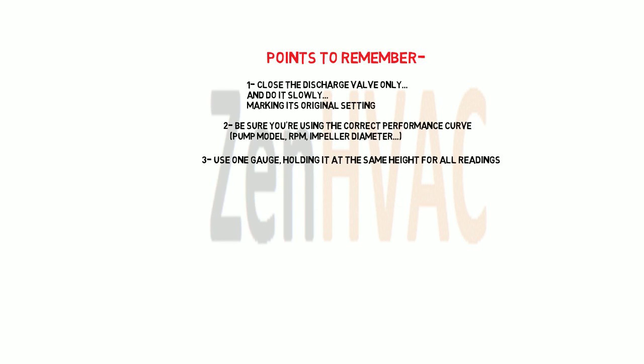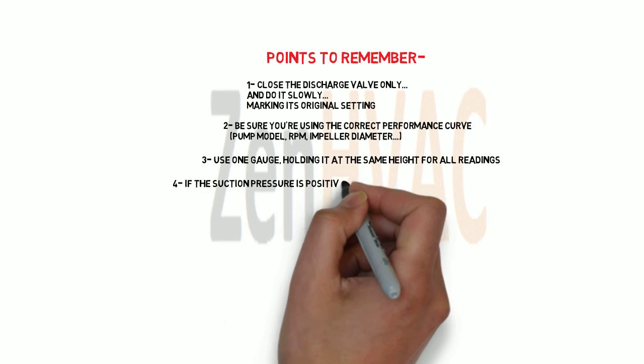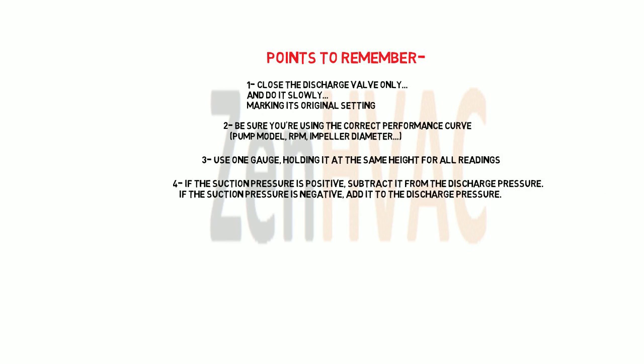Three, use one gauge, holding it at the same height for all readings. It makes a difference. Four, if the suction pressure is positive, subtract it from the head. If it's negative, add it.